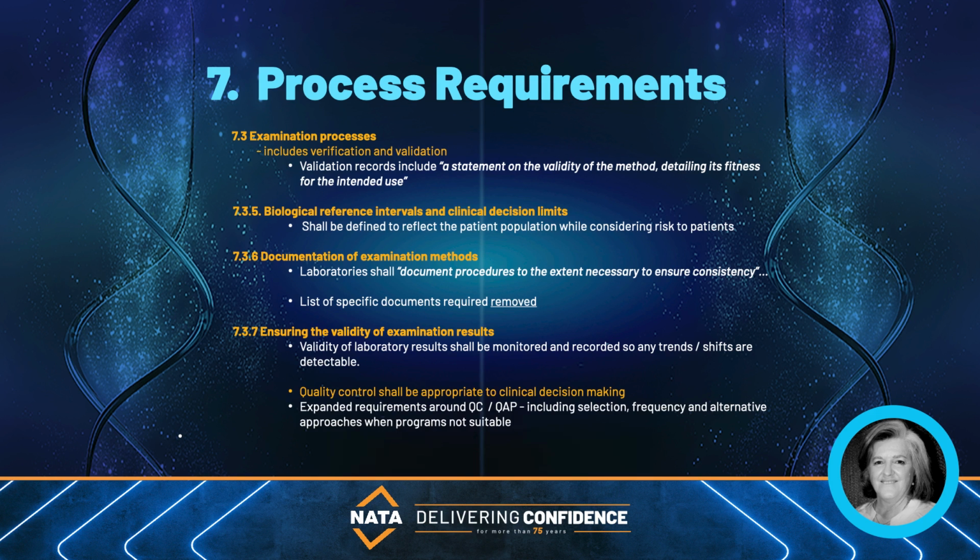QC frequency should be based on the stability and robustness of the examination method and the risk of harm to the patient from an incorrect result. QC data should be reviewed at regular intervals that allows for a meaningful identification of current performance. In the event of QC failure, the lab shall prevent the release of patient results.